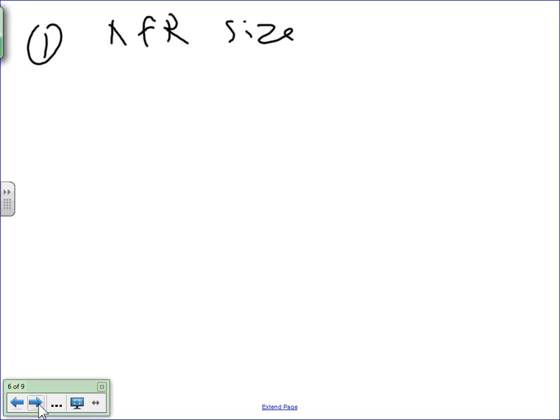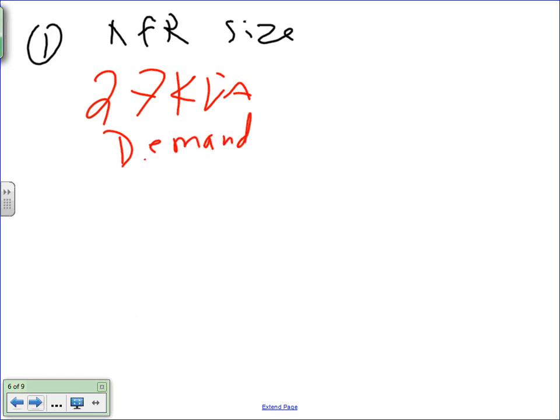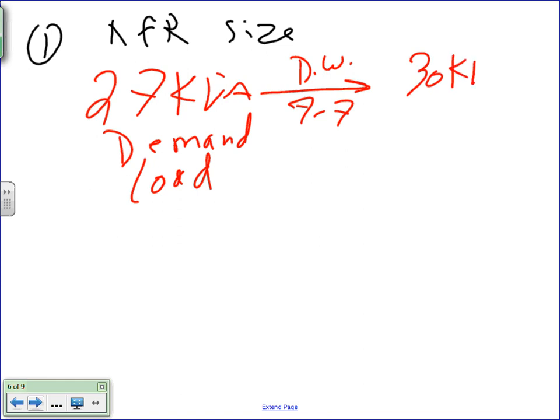Now I'm going to go directly and size my transformer. So remember that 27 kVA, the demand load. Based on the demand load, guys, you're going to go to the table, 27, Chris, 27. Yeah. And you're going to go, what's the next standard? 30. 30 kVA. And I hope you guys know how to use that. Yes, sir. Phil?